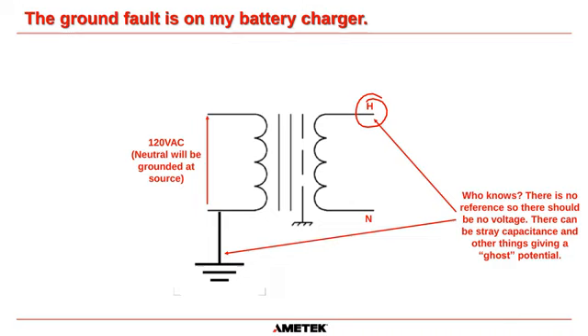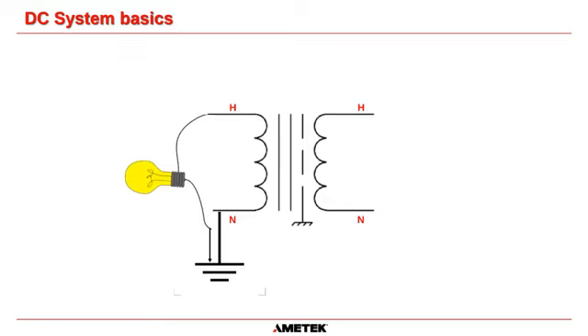But unfortunately, there can be stray capacitances, especially in plants where cable trays hold numerous cables, and you can get stray capacitance, inductance. You can get a ghost potential on there theoretically. But if you put any kind of light load between that cable and ground, it will dissipate. Okay, but in truth, there is no potential between the hot and the ground, and that is exactly the same for the neutral and ground. Okay, there's going to be no potential. I'm trying to drive this in so you understand the importance of the isolation transformer.